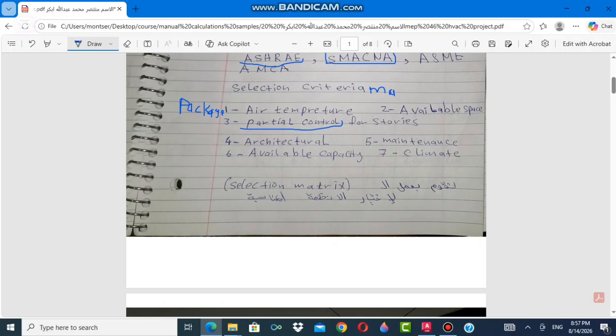You will also take architecture into consideration, because some systems aren't convenient for buildings more than 5 stories - even the packaged unit, because it has a big duct which could not be installed in a very high building. When the building becomes very high, the duct becomes very big.